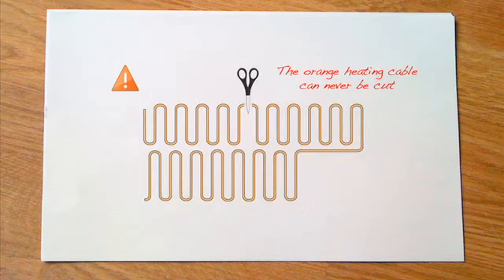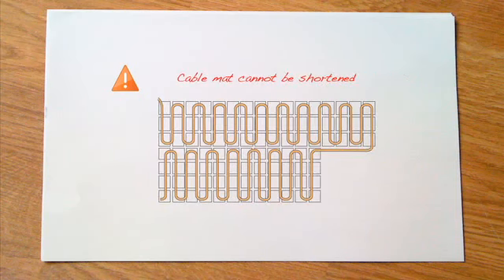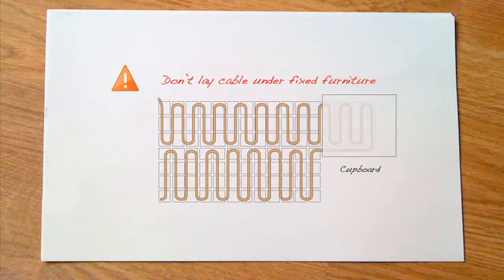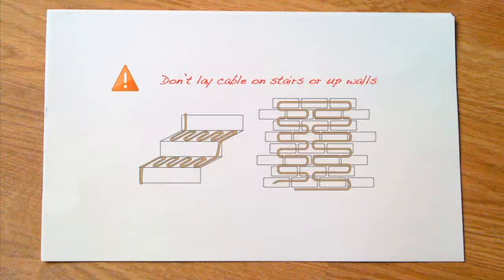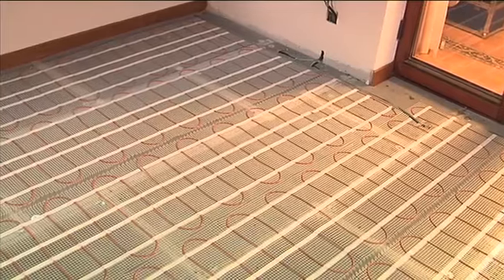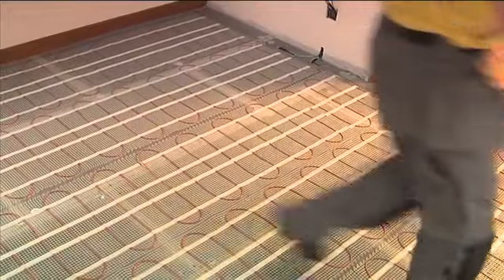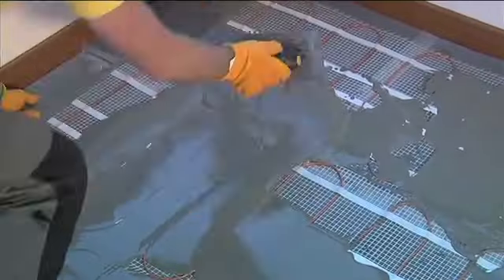The orange heating cable can never be cut. The heating cable mat can never be shortened. Don't lay the heating cable under any fixed furniture. Only install the cable mat on one level, never on stairs or walls. Cover the cable mat installation with a suitable latex self-leveling compound. This will provide a flat surface for the chosen floor covering.